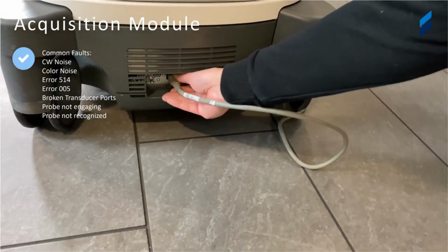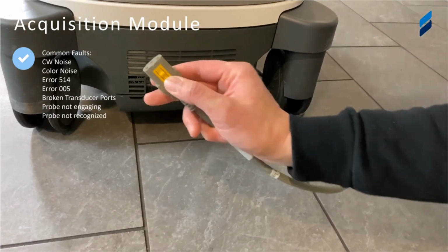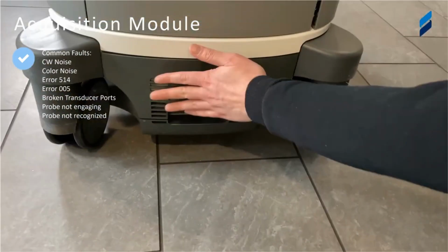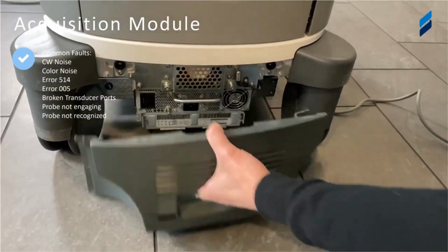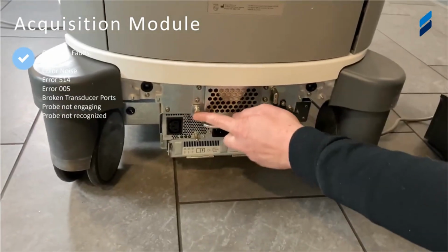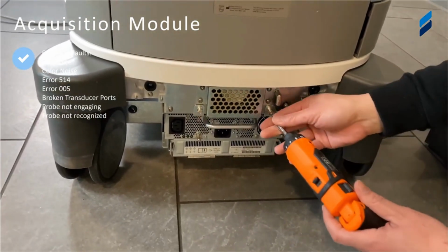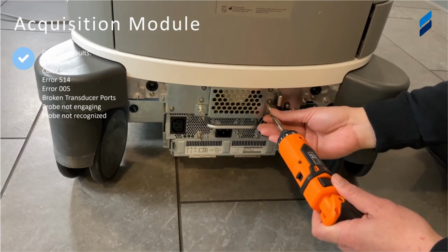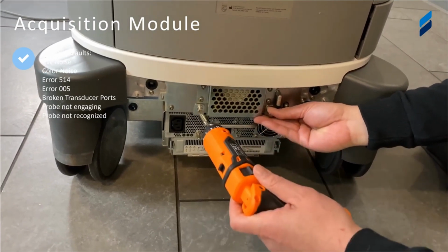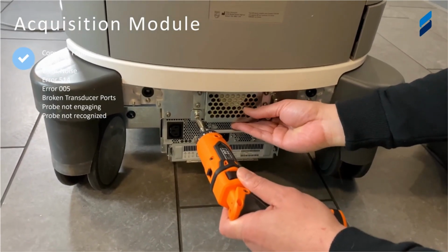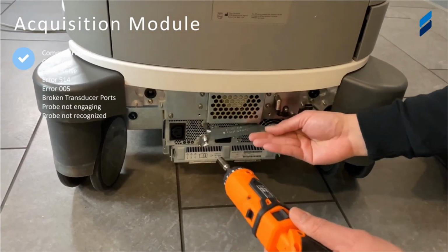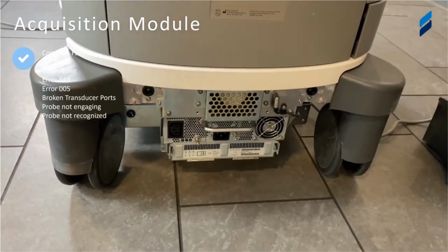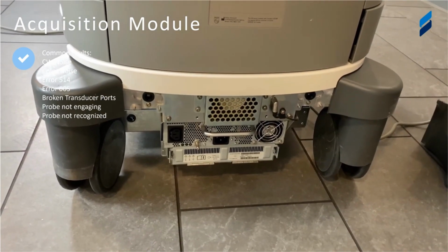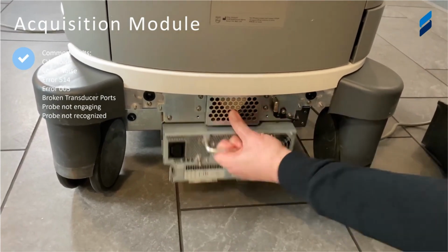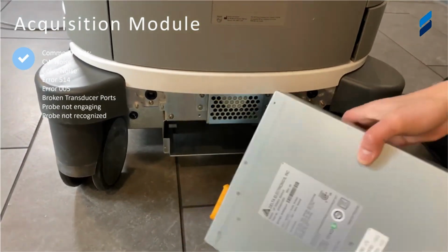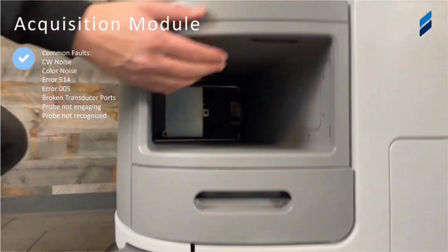We're going to start off with the acquisition module. This is the most common failing part in the machine, as we talked about before. The most common faults here are CW noise and color noise, like we talked about. You'll get some hard error code faults, 514, 005. Also included are broken transducer ports, which do happen, or probes not engaging or probes not recognized because there's something faulty in the probe identification circuits that are on there.